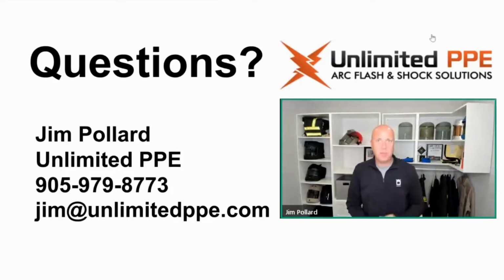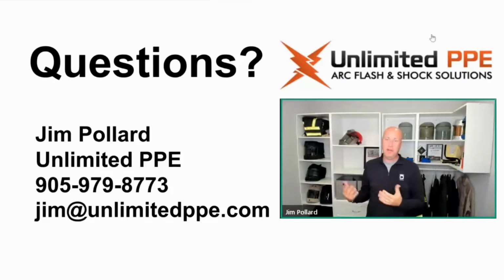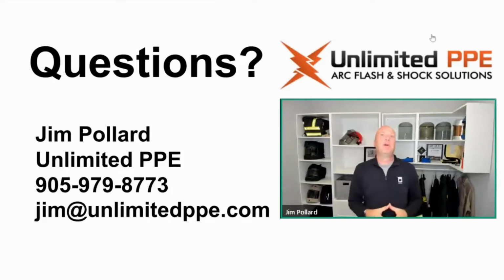I know Hugh Hoagland has done one, and there are others that I can think of, that have related to the pressure to containment. The moment you open up a door or remove a cover, you have removed, or mitigated, I should say, this pressure vessel that's created by an enclosed space and an arc flash occurring. Most electrical work is done with the door open or cover off. So therefore, we've mitigated that pressure or containment issue related to blast pressure.